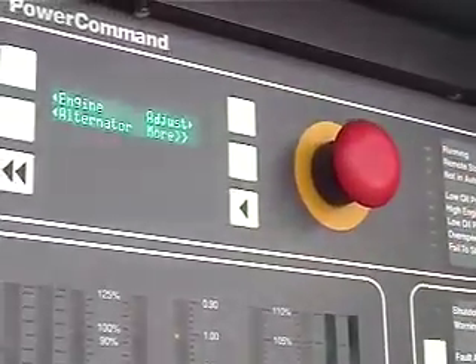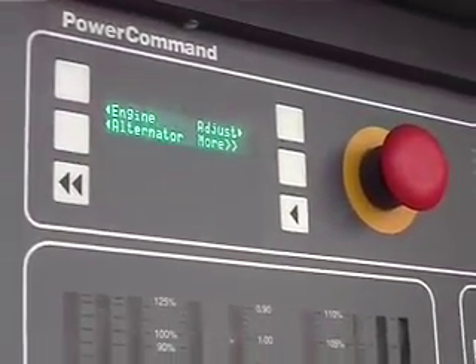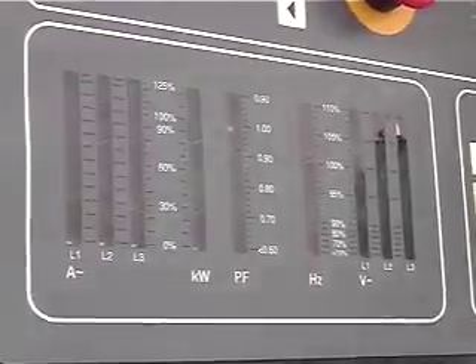Okay, so the very first thing is the very basic buttons and stuff on this control. You have this auto manual off button here. You got this big red e-stop button, and then the digital display and the analog display. Obviously it needs to be in auto to work automatically, just like any other generator that's out there. If you take it out of auto and turn it to manual, it will not start automatically from the transfer switch. Power goes out, it's just going to sit here looking nice.